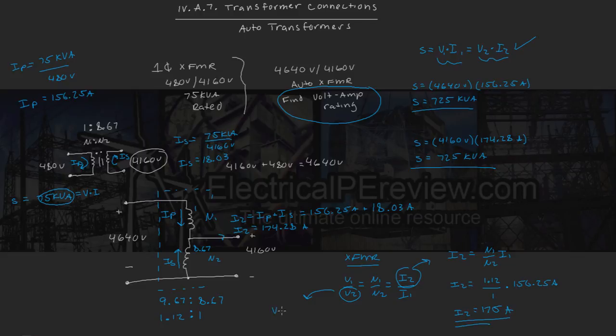So we can rewrite this as saying V2 equals V1 times N2 over N1, which is, we know our input voltage is 4640, that's the voltage we're regulating down, times our new secondary winding count, which we simplified as 1, over our new primary winding count, which we simplified as 1.12. We run these numbers and we should come up with 4160. Let's see. So V2 gives us, doing the numbers exactly, we get 4142.86, which is likely a little off from a rounding error, but for the most part, that's going to give us our 4160 value.